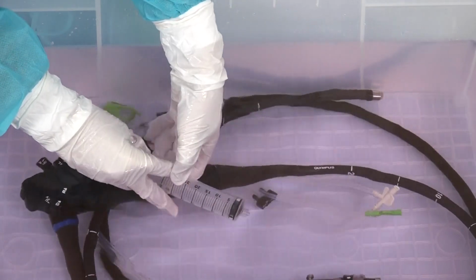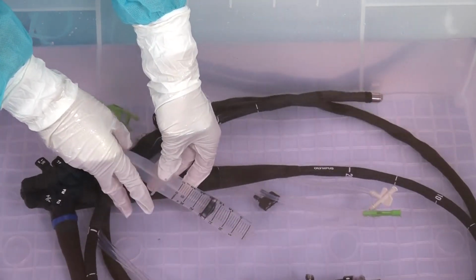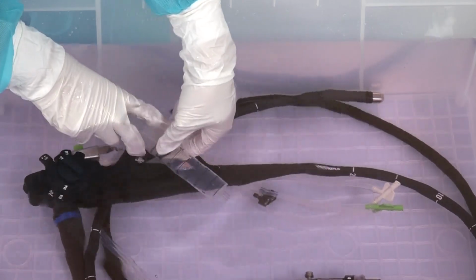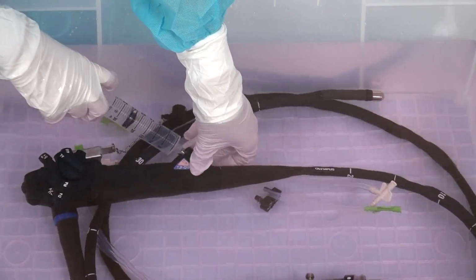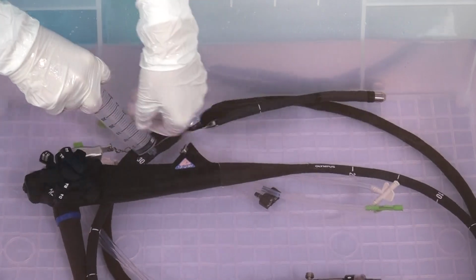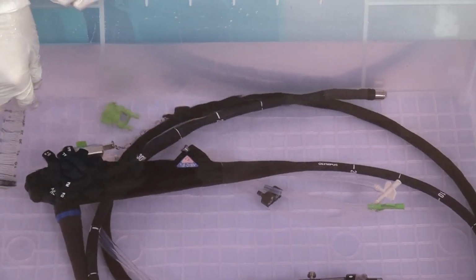Confirm that no air bubbles exit the distal end during the last flush. If air bubbles still exist, flush the channel with the disinfectant solution until no air bubbles exit.